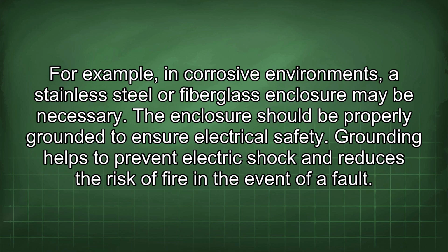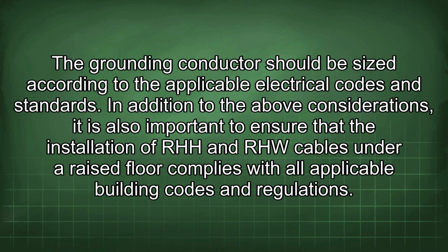Grounding helps to prevent electric shock and reduces the risk of fire in the event of a fault. The grounding conductor should be sized according to the applicable electrical codes and standards. In addition to the above considerations, it is also important to ensure that the installation of RHH and RHW cables under a raised floor complies with all applicable building codes and regulations.